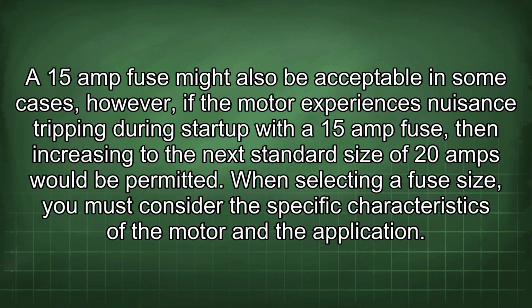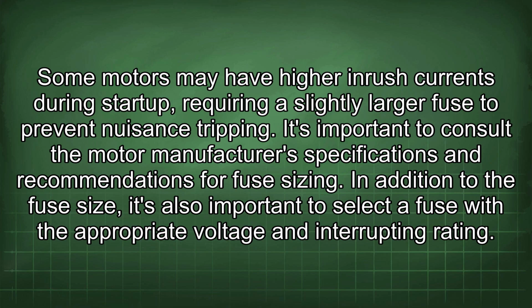A 15 amp fuse might also be acceptable in some cases. However, if the motor experiences nuisance tripping during startup with a 15 amp fuse, then increasing to the next standard size of 20 amps would be permitted. When selecting a fuse size, you must consider the specific characteristics of the motor and the application. Some motors may have higher inrush currents during startup, requiring a slightly larger fuse to prevent nuisance tripping. It's important to consult the motor manufacturer's specifications and recommendations for fuse sizing.